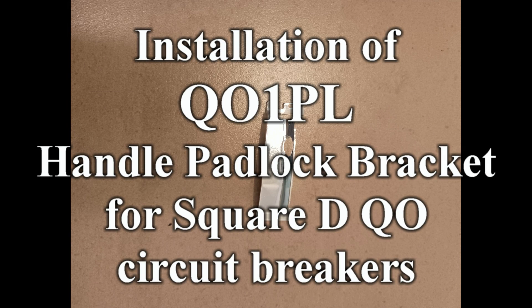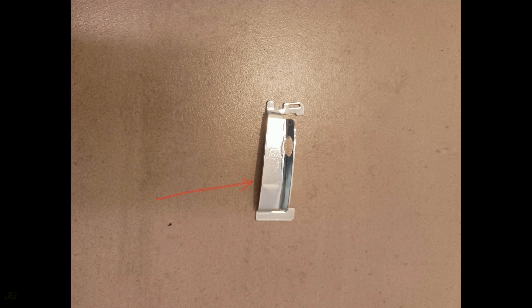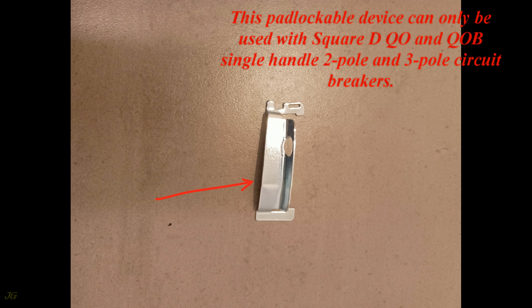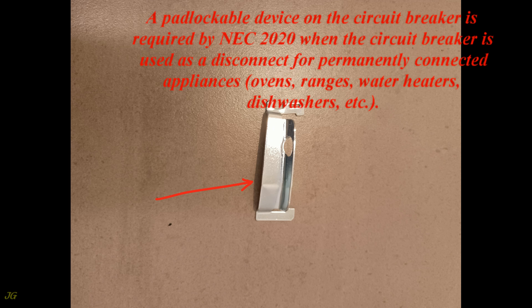Installation of the QO1PL Handle Padlock Bracket for Square D QO circuit breakers. This padlockable device can only be used with Square D QO and QOB single-handle 2-pole and 3-pole circuit breakers. A padlockable device on the circuit breaker is required by NEC 2020 when the circuit breaker is used as a disconnect for permanently connected appliances.